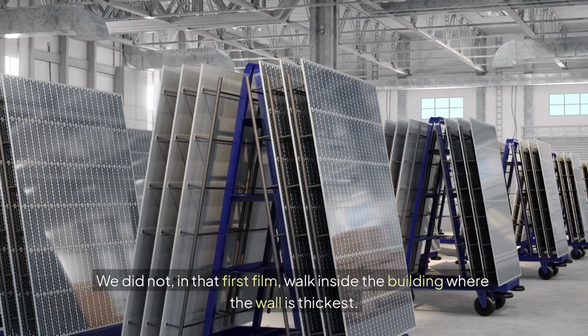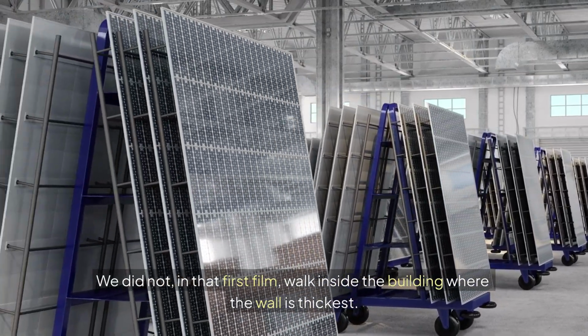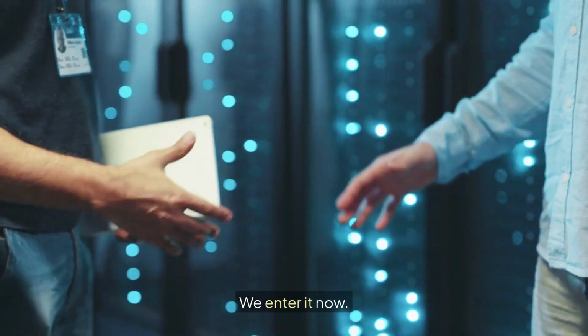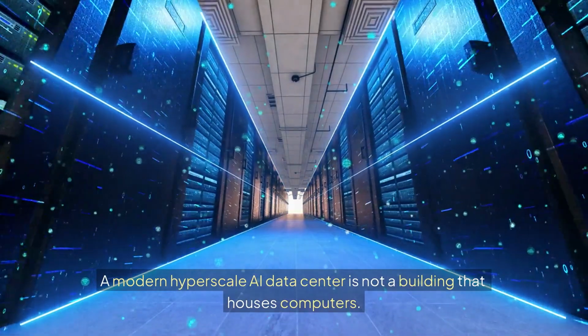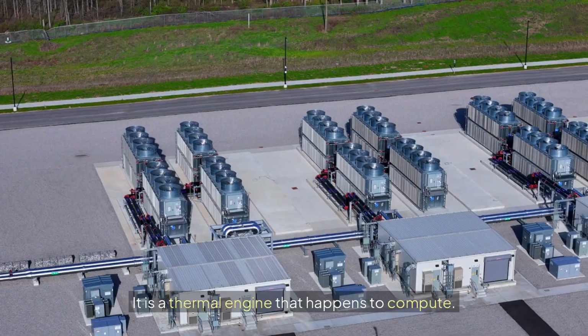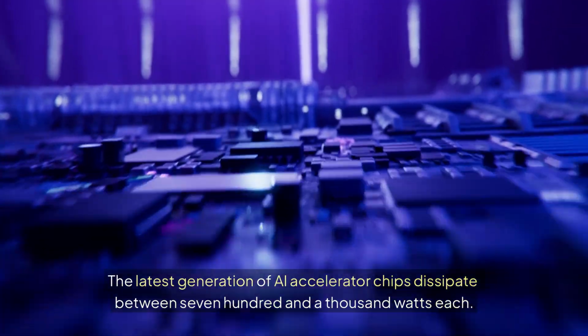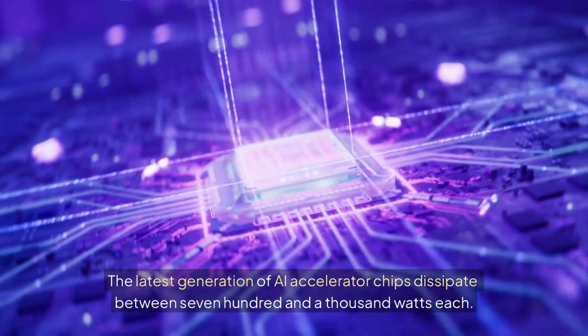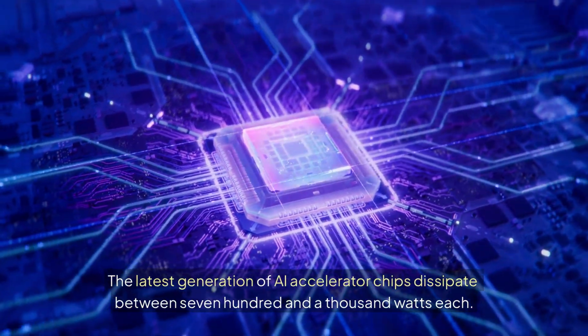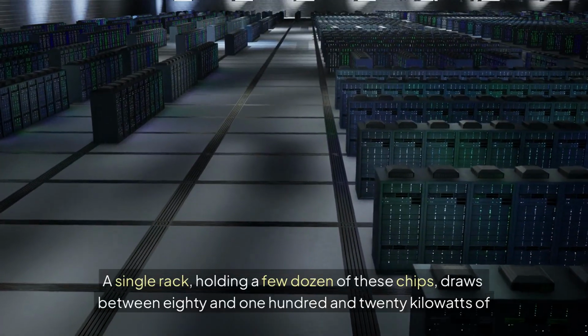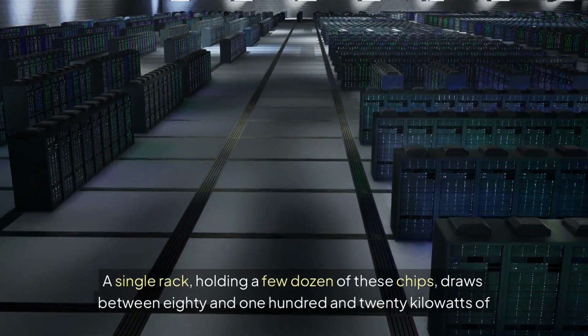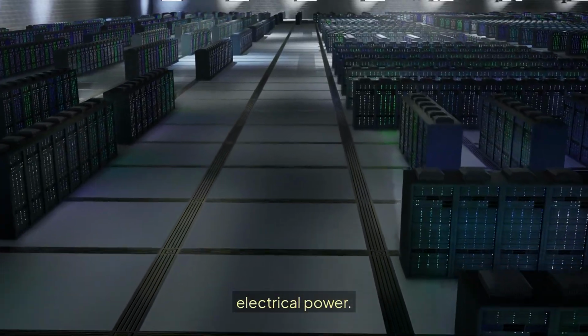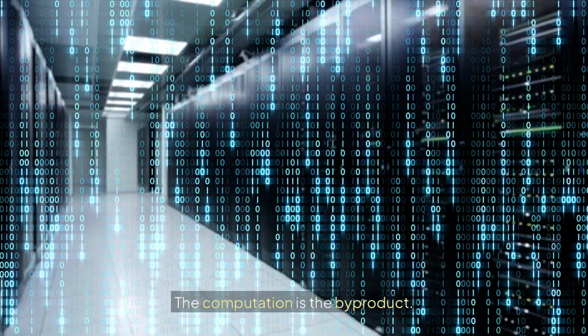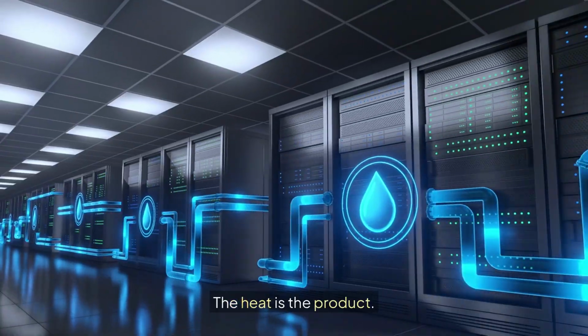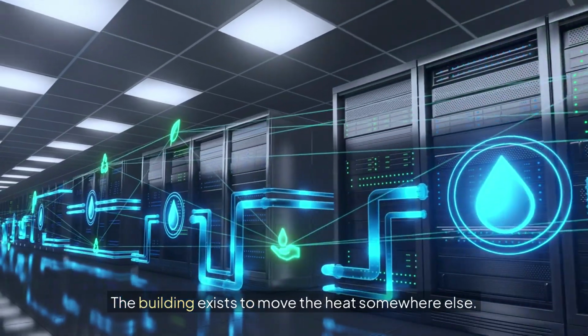We did not, in that first film, walk inside the building where the wall is thickest. We did not enter the data center. We enter it now. A modern hyperscale AI data center is not a building that houses computers. It is a thermal engine that happens to compute. The latest generation of AI accelerator chips dissipate between 700 and 1,000 watts each. The generation arriving by 2028 will dissipate over 1,200. A single rack, holding a few dozen of these chips, draws between 80 and 120 kilowatts of electrical power. Nearly all of that power becomes heat. The computation is the byproduct. The heat is the product. The building exists to move the heat somewhere else.